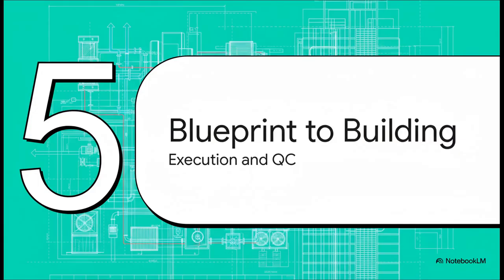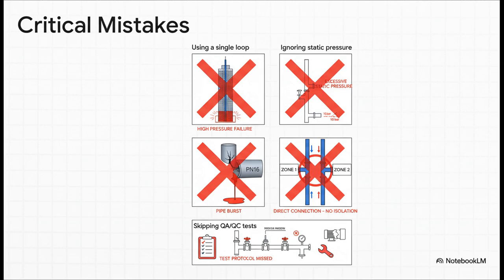You know, a perfect design on paper is completely worthless if it isn't built right. So this final phase is all about what happens on site. It's about execution, it's about quality control, and it's about making sure the thing that's in the drawings is what actually gets installed. So let's just quickly recap the absolute cardinal sins of high-rise HVAC design. Trying to run a single loop, ignoring static pressure, using underrated pipes, skipping the heat exchangers. These aren't just little oopsies. These are guaranteed failures that will violate a whole stack of codes and standards. You just can't do it.